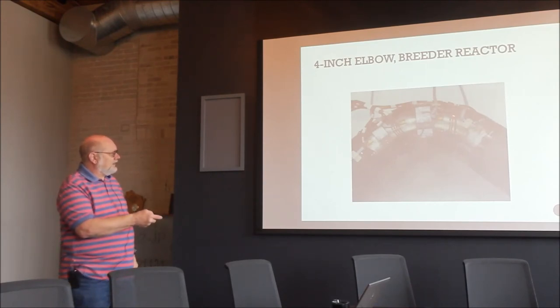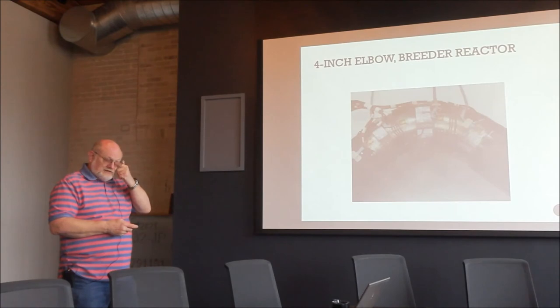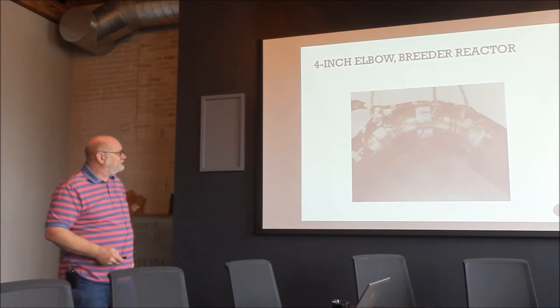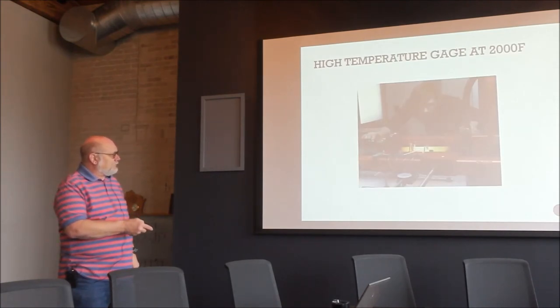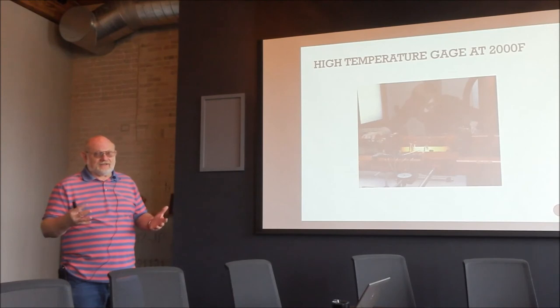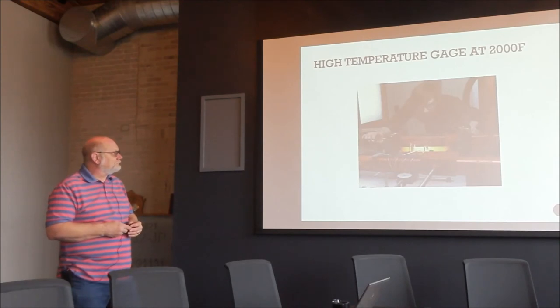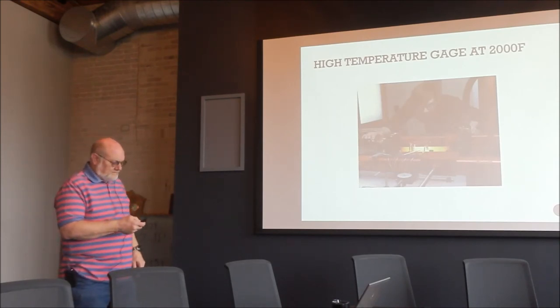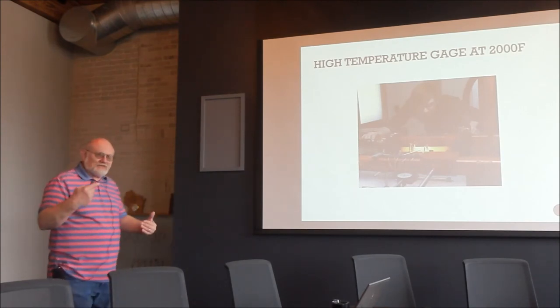A piece of plumbing from a breeder reactor was instrumented with both foil gauges to examine principal strain at room temperature and free-filament high-temperature gauges to measure conditions during operation. Separately, an investment-cast IN-100 bar was tested with direct resistance heating and free-filament gauges, not testing the bar but testing the gauges themselves for thermal shock at heating rates up to 70°C per second.